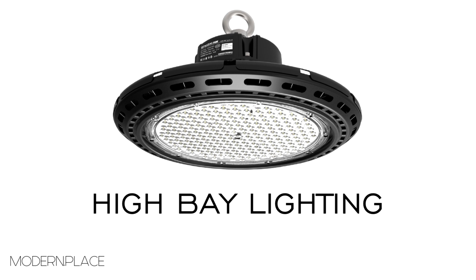Next, we're moving on to the beam angle. Generally, almost everybody gets a 120 degree beam angle unless their high bays are really high up and they need more luminous flux per square foot. At that point, they either move down to a 90 or 60 degree beam angle, which is just a narrower, brighter light. For most applications from 14 to 25 to even 30 feet, 120 degrees is just fine. You generally want to spread the light and have each of the lights overlap each other at least a bit, so there's even lighting across your whole warehouse.